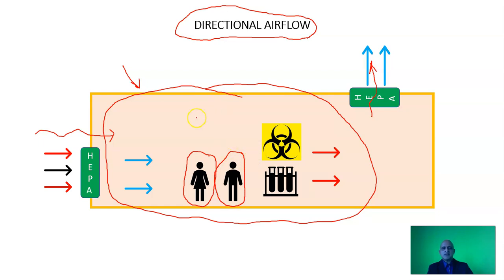In a general containment facility, the air is directed into the facility via HEPA filters and enters as filtered air. It then flows through the facility over the biological agent and is filtered prior to release into the environment. This ensures that the criteria for secondary containment are met and that the community is not exposed to any escaped biological agent.